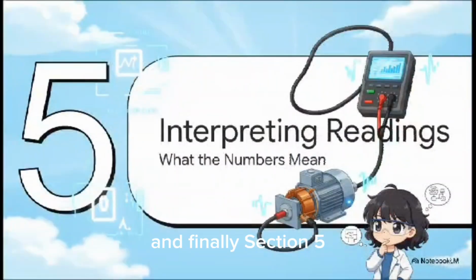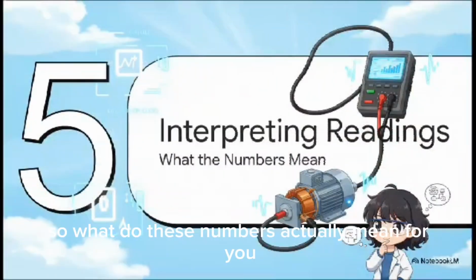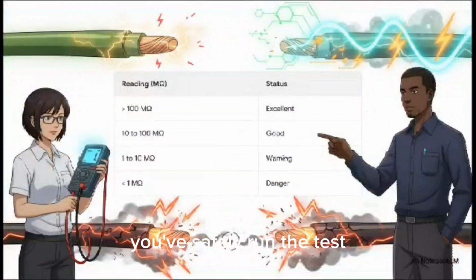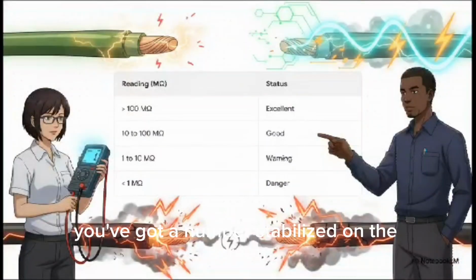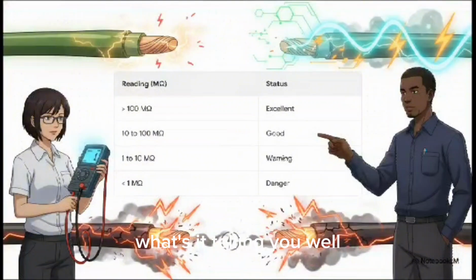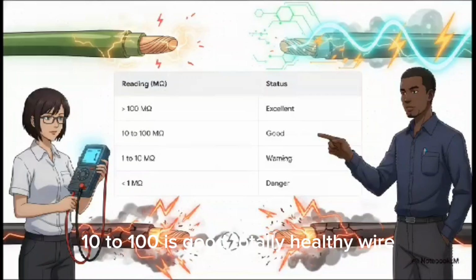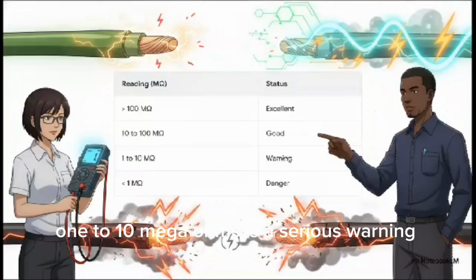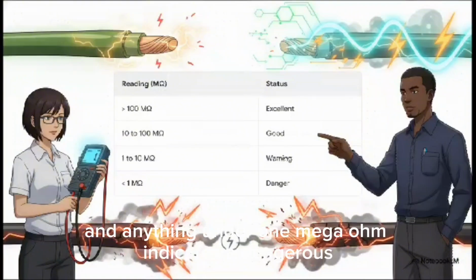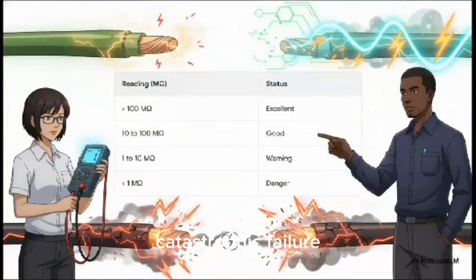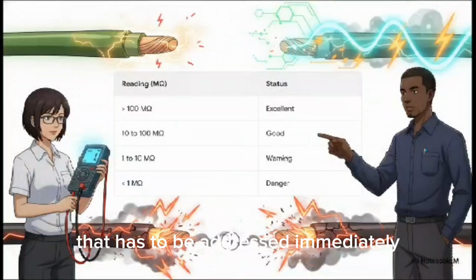And finally, Section 5, interpreting resistance test readings. So what do these numbers actually mean for you? You've safely run the test, you've got a number stabilized on the screen. What's it telling you? Well, a reading of over 100 megaohms, that means your insulation is excellent. 10 to 100 is good, totally healthy wire. 1 to 10 megaohms is a serious warning sign that degradation is actively happening right now. And anything under 1 megaohm indicates a dangerous, catastrophic failure that has to be addressed immediately.